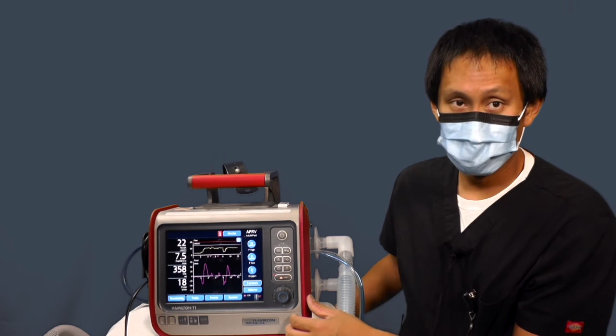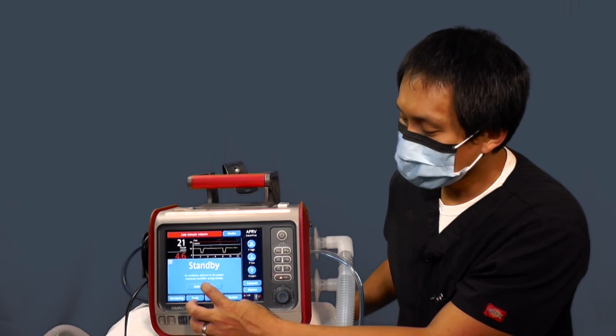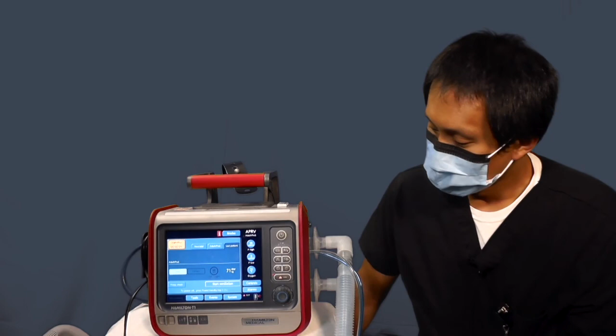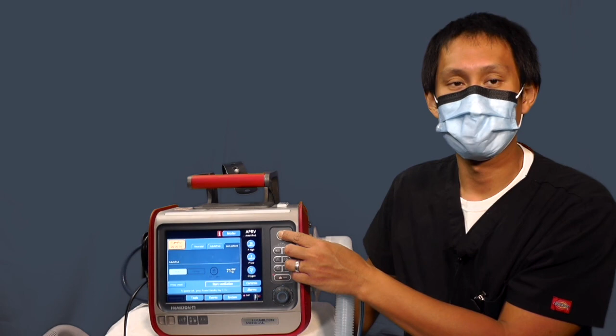To put this ventilator on standby, you want to hit that power button, and you'll have a standby menu that'll come up. Double confirm by activating the standby, so it will not just go into standby accidentally or turn off if you hit the power button. To turn this machine off, what you're going to do is get it into the standby page, which is this page or the home page, and then hit the power button for 3 seconds, and then it'll shut off.